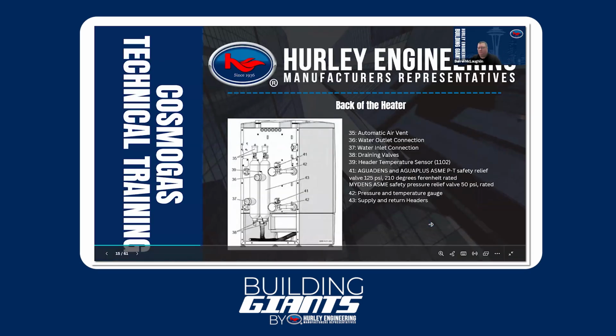Okay, the back of the heater. Just to familiarize with what comes standard on every installation, I'll start from the top here. So 35 are just auto vents for easy bleeding of air, so you can purge them and charge them with fluid for the first time. Then we've got our header sensor that's pre-built in. You don't have to order that separately. That's already there. And then the water outlet connection, threaded connection, and inlet connection, again threaded, as well as drain connections down here on the bottom. So if you ever have to drain things down, that's where you would go.